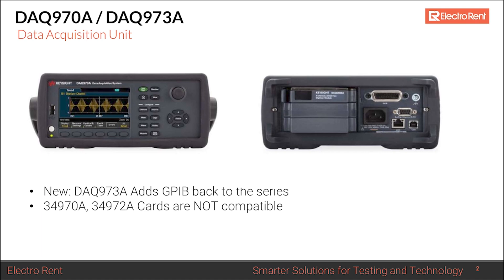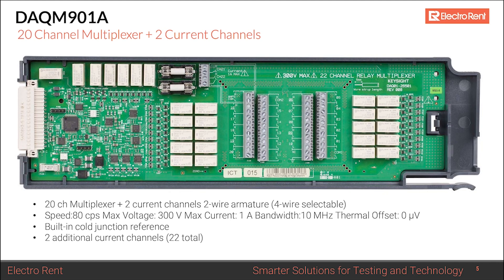The first card is the DAQM901A, similar to the legacy 34901A. It's a 20-channel multiplexer using reed relays and is the preferred card for thermocouples, with a thermal offset of zero microvolts. It has a built-in cold junction reference, 20 scanning channels for thermocouples, and additional channels for current measurements. It scans at 80 channels per second — reed relays need settling time — with a maximum of 300 volts and 1 amp.